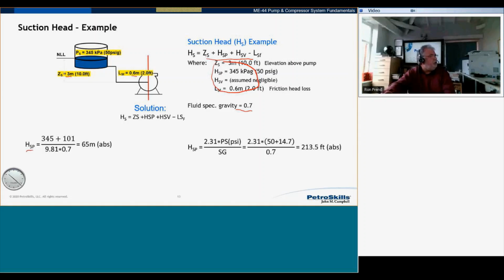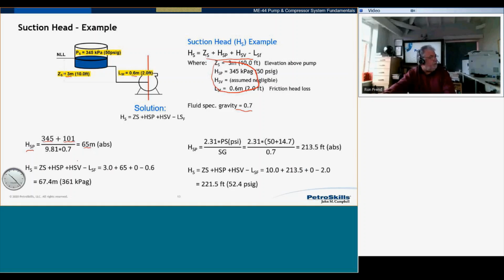So if we just concentrate on the SI units, the suction pressure, 345 kPa, I'm going to convert this to absolute. So I'm going to add the atmospheric pressure, 101.3 kPa. Anyway, that comes out at 65 meters. If we then add all this together, I've got my elevation head, which is 3 meters. I've got my suction pressure head, which is 65 meters. My velocity head I'm ignoring. The friction losses we said were 0.6. It gives us a suction head of 67.4 meters. Now, for those of you who like to work in feet, the same numbers are here on the right side.